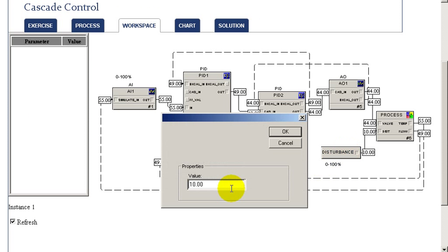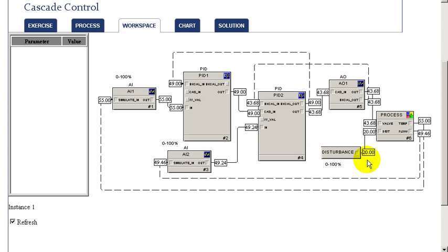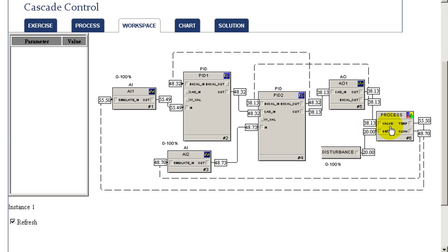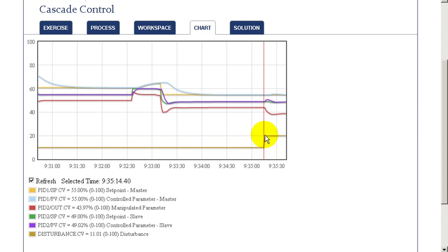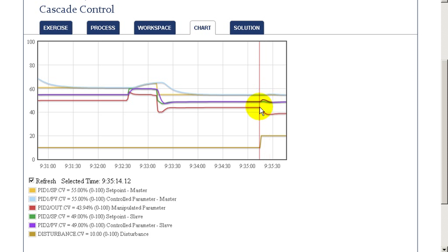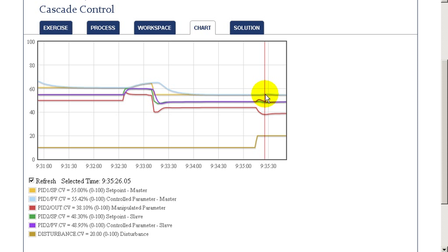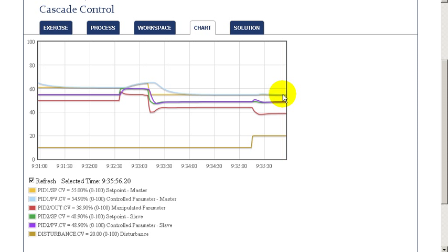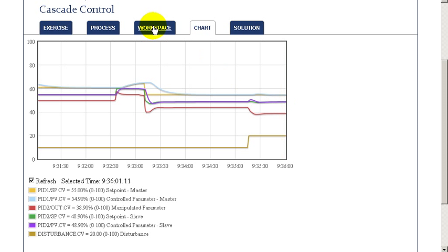We can look at the dynamic behavior when we introduce a disturbance into our slave loop. When we introduce a step change, it has an immediate impact upon the control parameter used by our slave loop. Since the slave loop is very fast in responding, it can quickly correct for that disturbance to maintain its target dictated by the master loop. Looking at the chart, when we introduce the disturbance, the slave loop very quickly adjusted its output to compensate. As a result, the control parameter of our master loop hardly varied at all from setpoint.